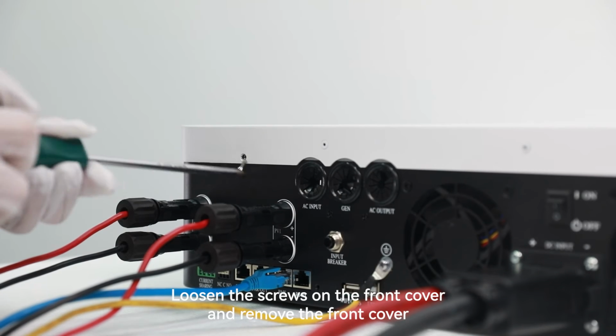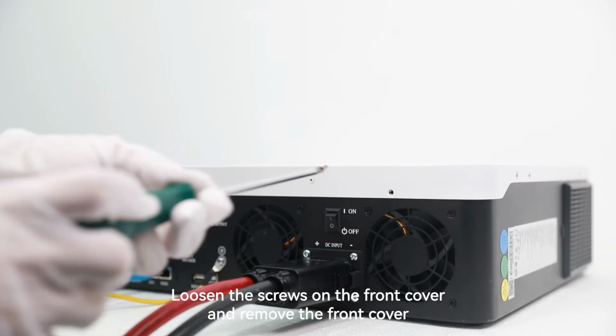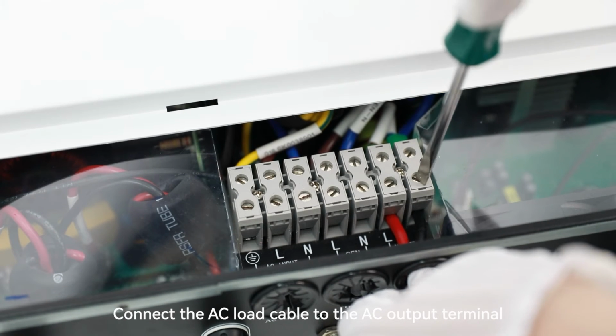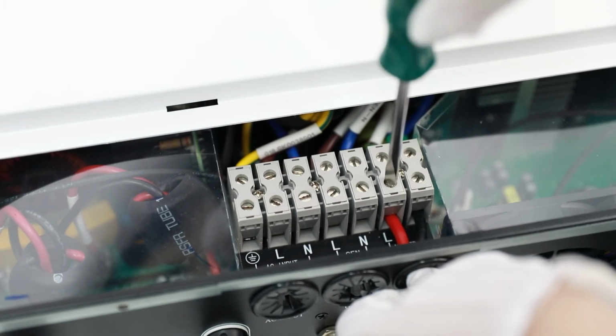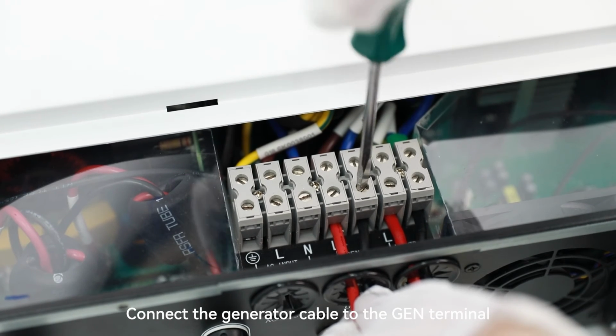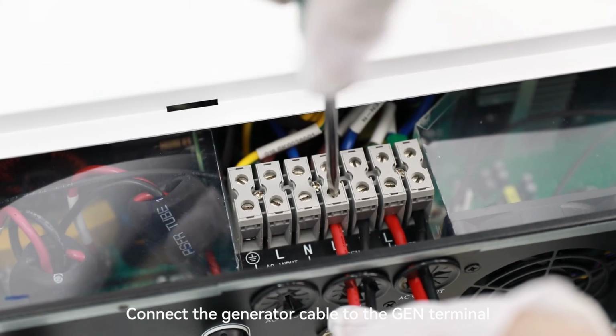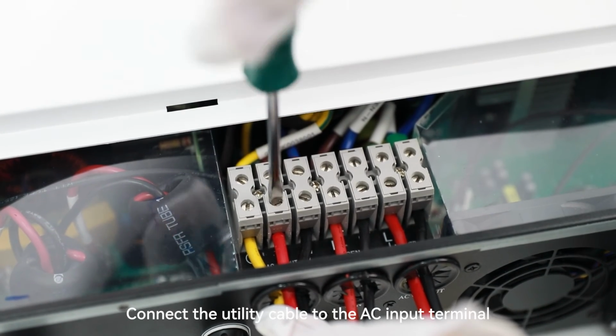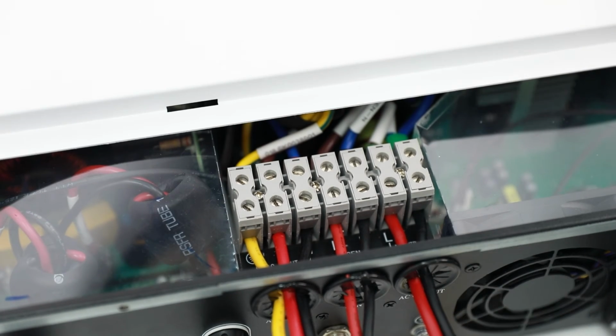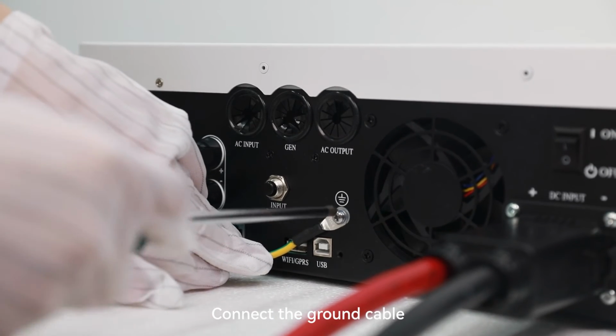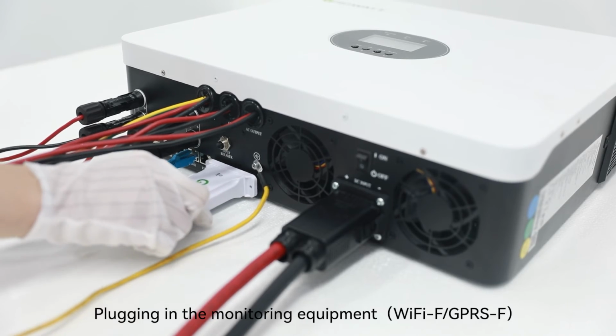Loosen the screws on the front cover and remove the front cover. Connect the AC load cable to the AC output terminal. Connect the generator cable to the gen terminal. Connect the utility cable to the AC input terminal. Connect the ground cable. Plug in the monitoring equipment.